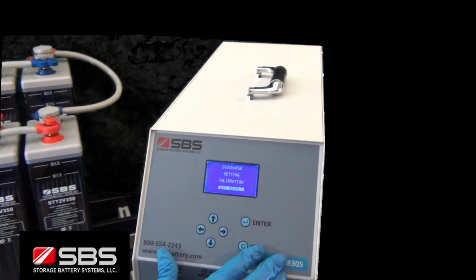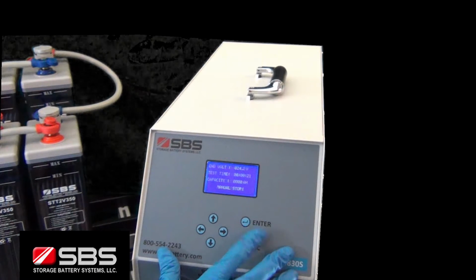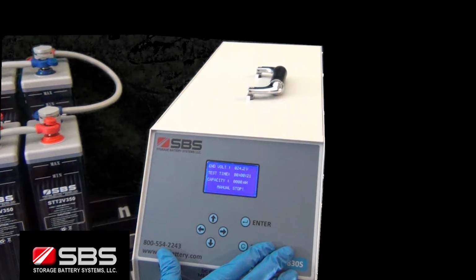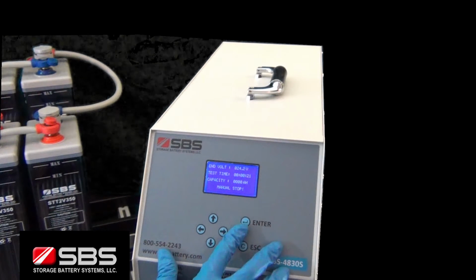When the test is complete, you can now check the test results of the discharge. Select Test Results on the main menu screen. The SBS S-Series will save the last discharge test result. The interface will show the test end voltage, total test time, capacity discharged, and the stop reason.